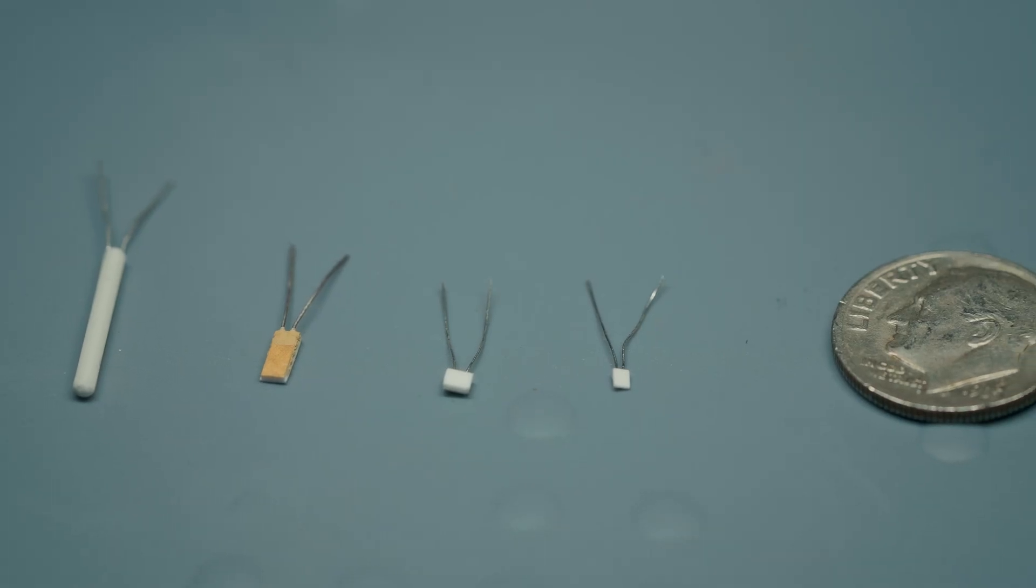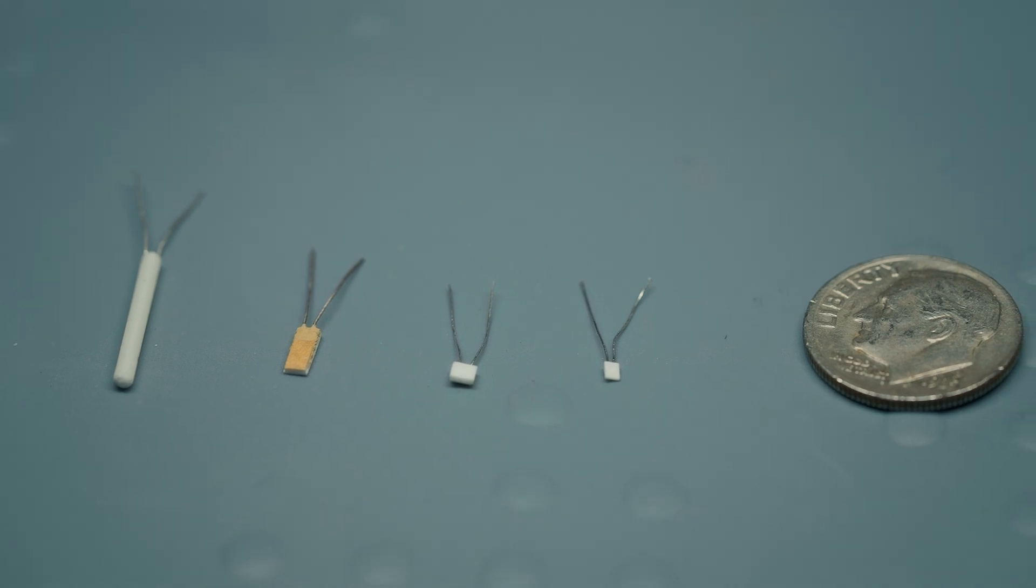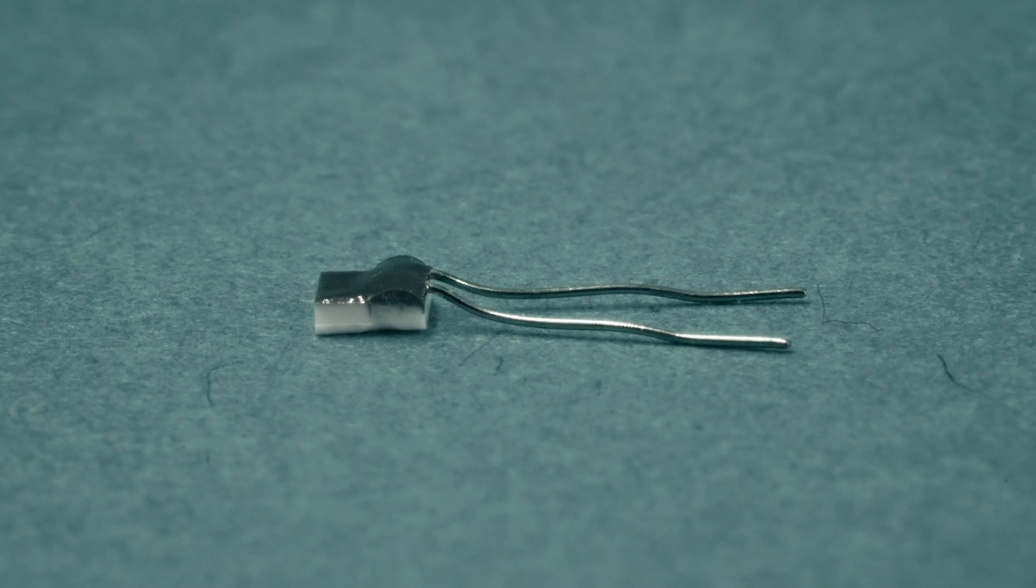If an RTD reads open at any point, or if the resistance is wildly different than the chart, then the RTD may be non-functional.